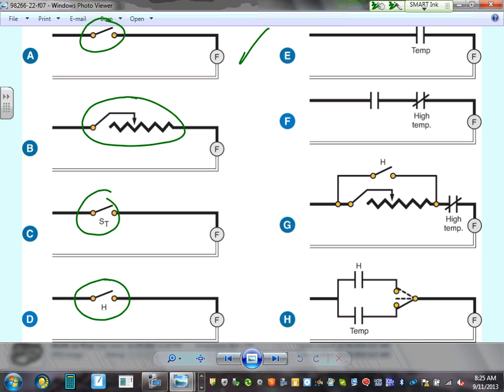E, if you look at E, temperature. This is temperature control. Like in an attic, when the temperature goes to 95, start exhausting. When it goes lower than that, stop. So there's a range for it. Does that make sense, guys? Then we have F, high temperature auto heater sensor with shut off. So we have a high temperature shut off. When the temperature reaches this value, so now when they add a high temperature shut off, a certain value will shut it off.